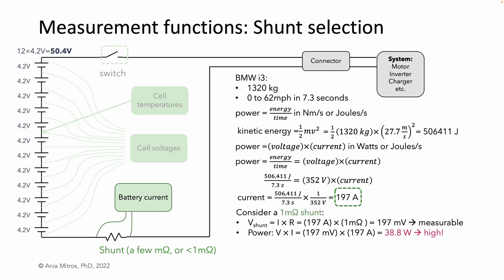For a 1 milliohm shunt, with 197 amps, we'll see 197 millivolts across the shunt, which is measurable. That's good. But we'll also see nearly 39 watts of power dissipation. That's a problem: the energy loss is inefficient, but more importantly, that much heating in a single component is problematic, and the shunt will get hot. Metal has a temperature coefficient, so a hot shunt will read differently than a room temperature shunt, giving poor current measurement accuracy. Remember, we wanted a precision resistor for a precision measurement.